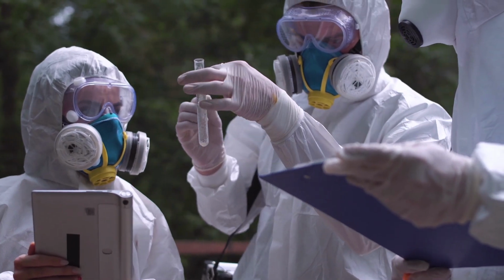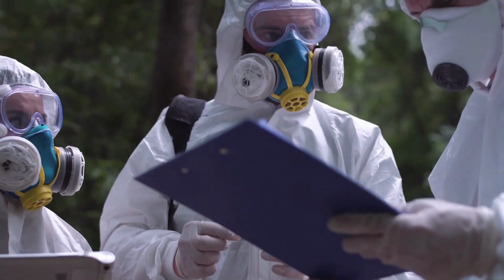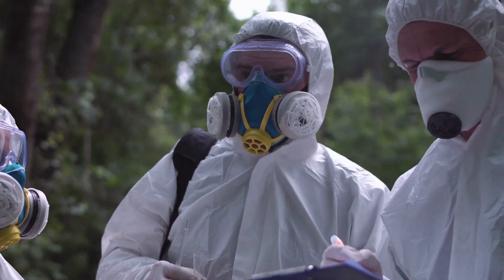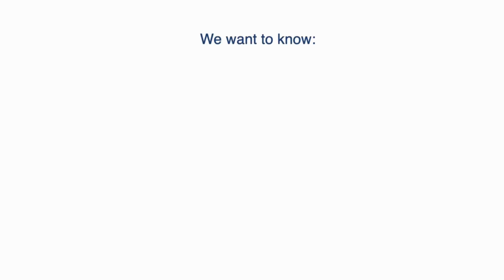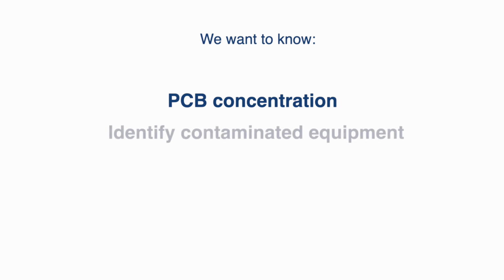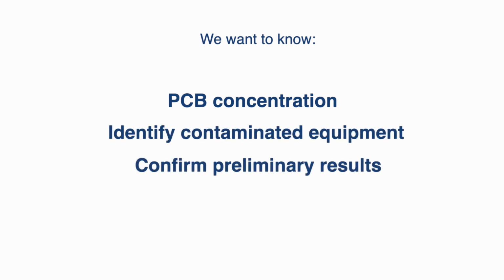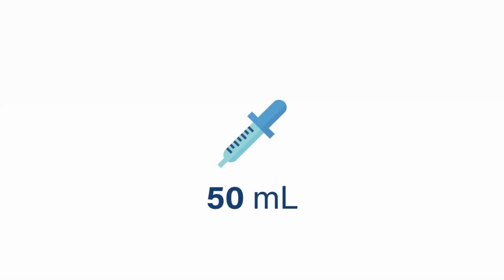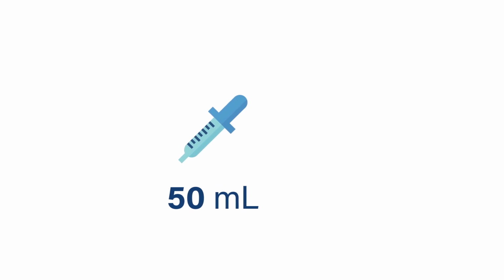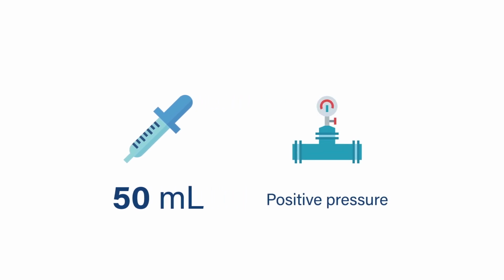Sampling. Sampling is an investigation tool where a portion that is representative of the oil is collected and analyzed. In our case, we want to know PCB concentration in the oils to identify contaminated equipment, as well as to confirm our preliminary results from previous inventories. Usually around 50 milliliters are sampled. Oil samples should be taken under positive pressure through the sampling valve of the transformer, which should be previously flushed.